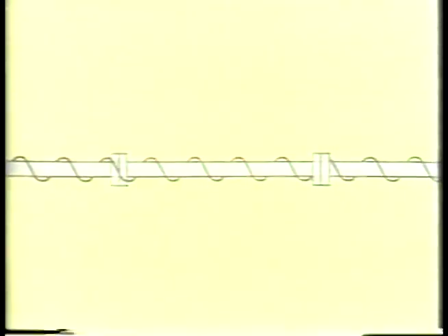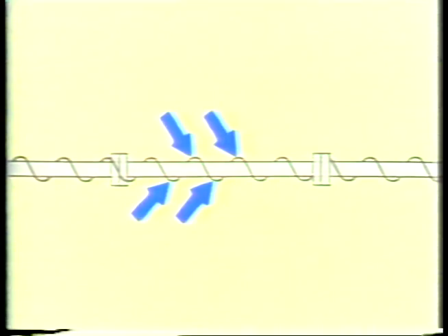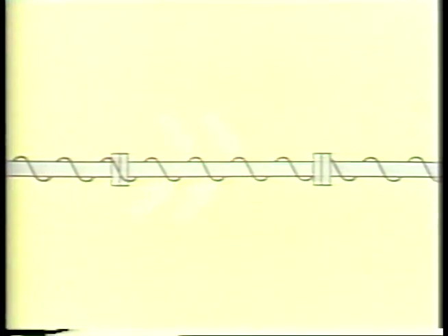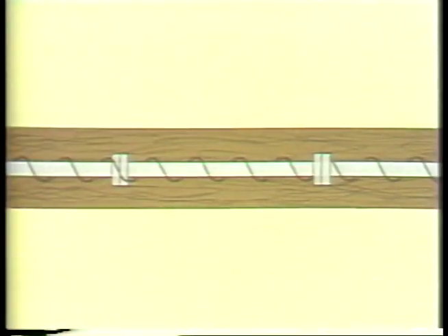For this reason, lines that carry water, which might be exposed to low temperatures, are usually heat-traced to prevent freezing. There are two ways that a pipe can be heat traced: electrical heat tracing or steam heat tracing. Lines that are electrically heat traced are wrapped in a special tape that has an electrical heating element in it. The tape provides just enough heat to prevent the water in the pipe from freezing. The tape is made more effective by wrapping insulation around the pipe and the heat tracing.